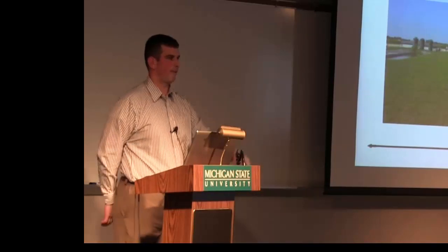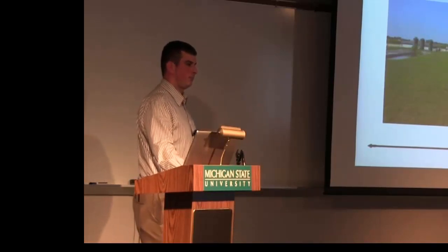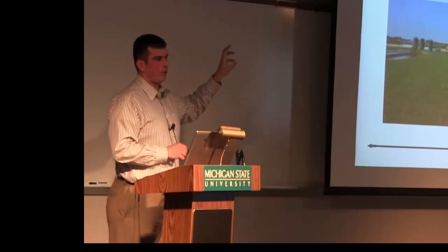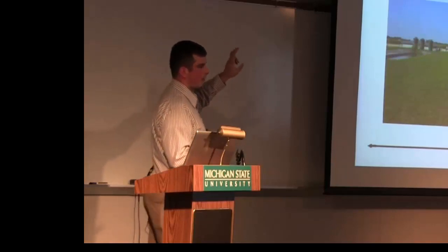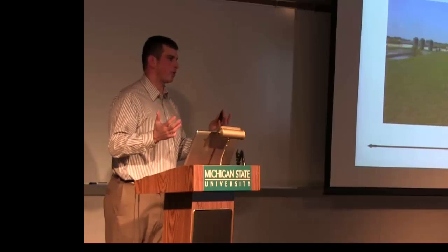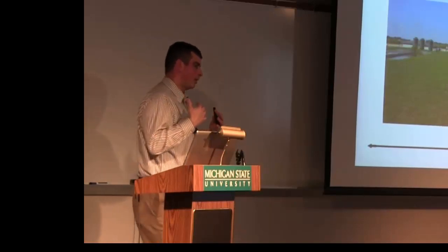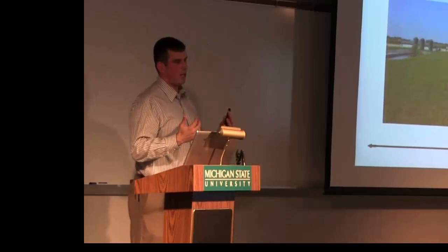Have you done any studies on residential or human waste compared to cow manure and energy? Yes, a little. And how's it compare? We're all animals, but cows digest a lot differently. There's a lot of charts out there on this comparison of energy densities. There's a really good one that's been done out of Germany. When you look at it, I probably misspoke on the energy density of manure. Dairy manure is 30 to 50 cubic meters per ton, typically, of biogas potential. Human waste in a raw form would be slightly higher because we're eating a slightly richer diet, but it is in that same order of magnitude. So we may be 50 to 80 cubic meters per ton of energy potential from human waste, still well below materials that are raw in nature.